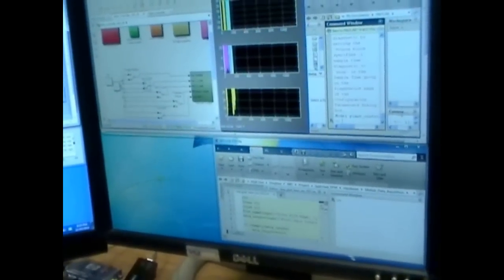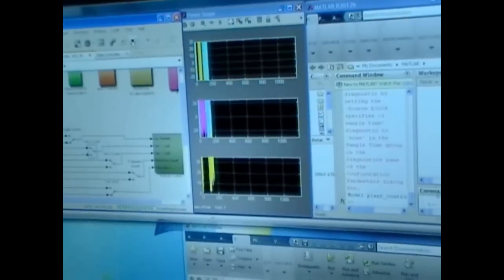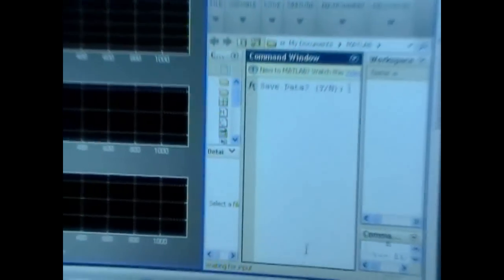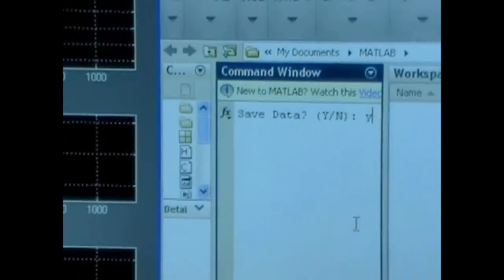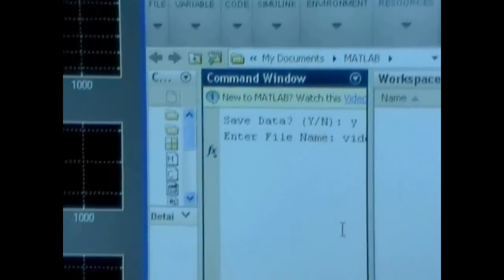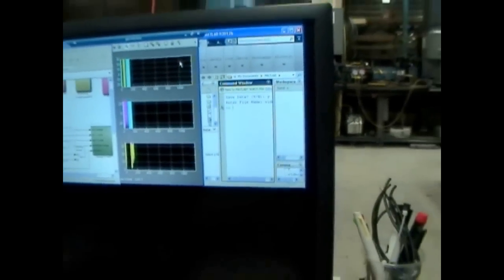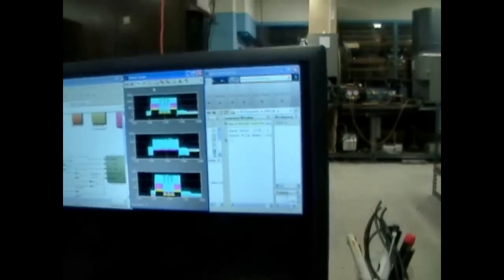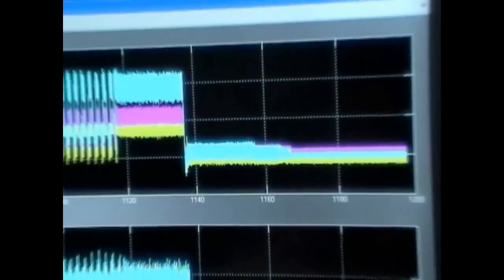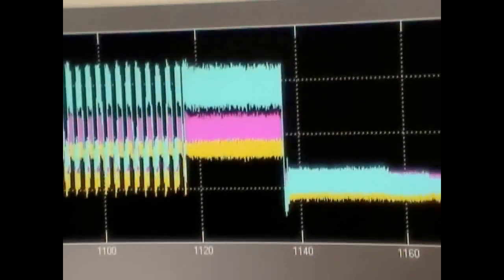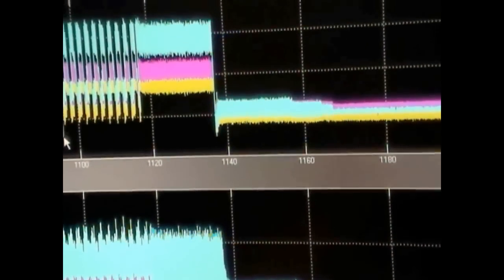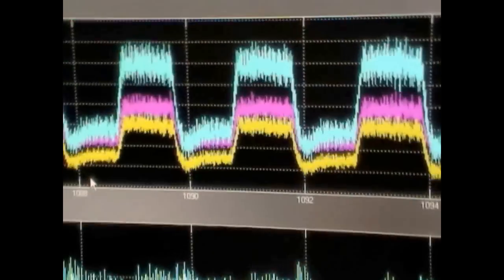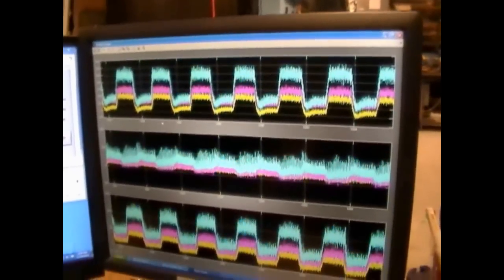So as we stop the setup, you can see here we are throwing off the bus voltage, and again we can plot all the parameters from the MATLAB. So you can see here the power supplied by the generators. The pink is one of the generators and yellow is the other generator, and the sum total is the blue one. And this was essentially the point where we loaded the generator in a pulsating manner, when we were emulating that the propeller is going in and out of water. And this is where we ramped it up from 0 to 1800 RPM.